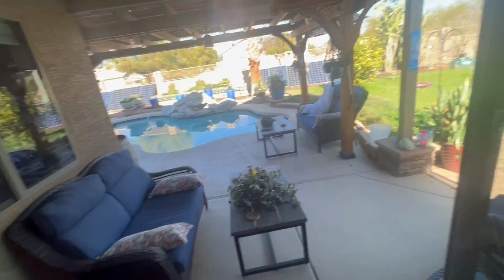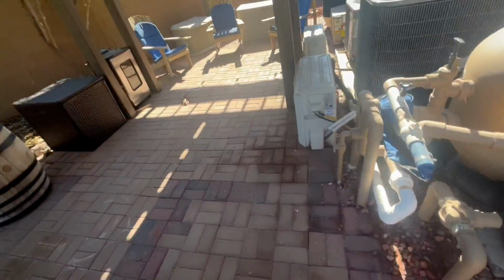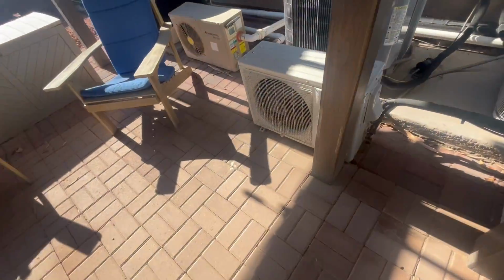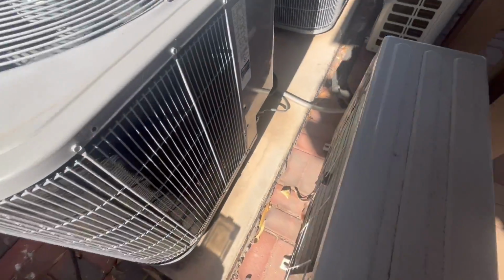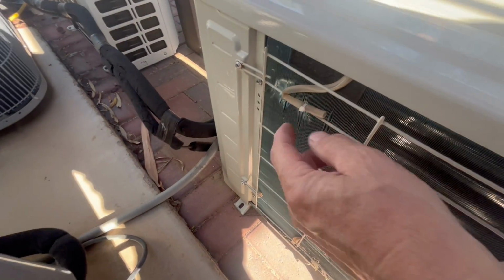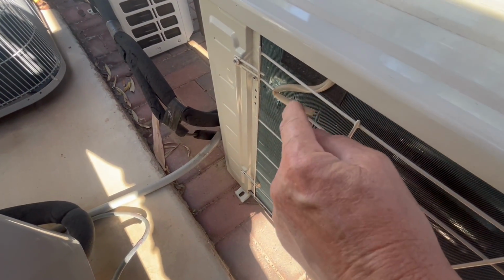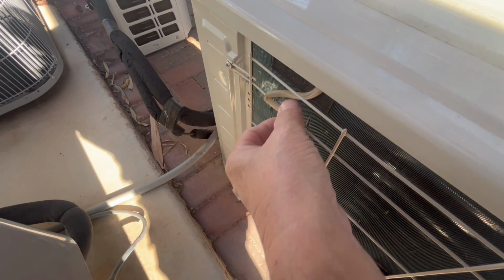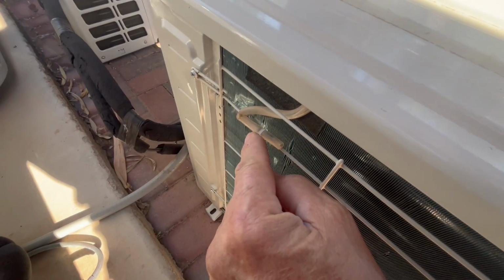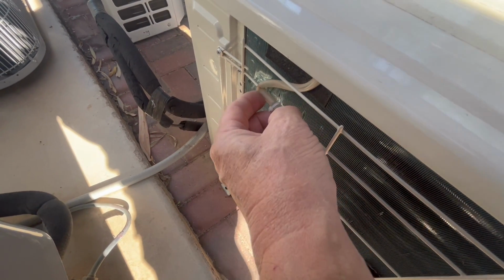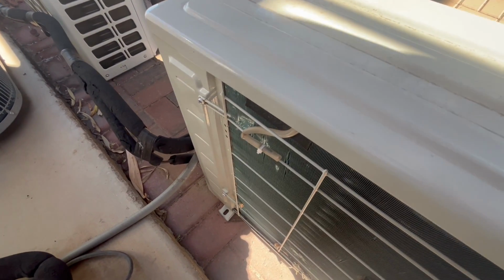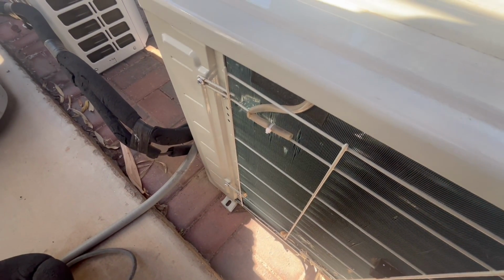There's actually a temperature sensor on this outside unit, right over here - there's a temp sensor unit right there. If you get an F1 error, you might want to check this. You might have to clip this thing off here, pull that tubing out a little bit, and clean it to see if that's having a problem. If it's really dirty, it may not sense it.